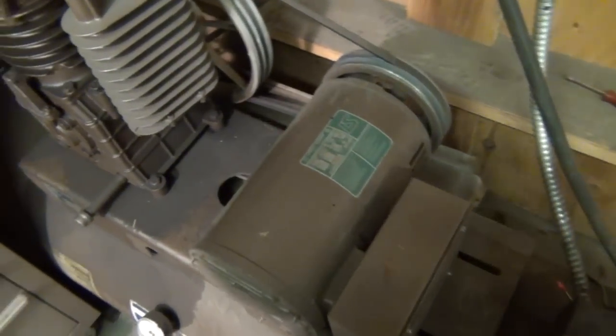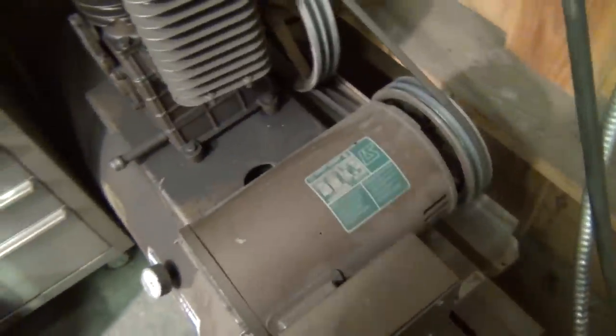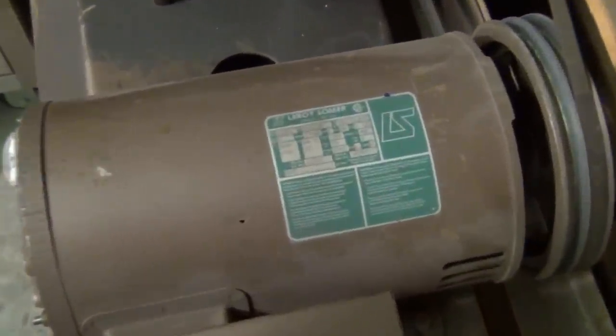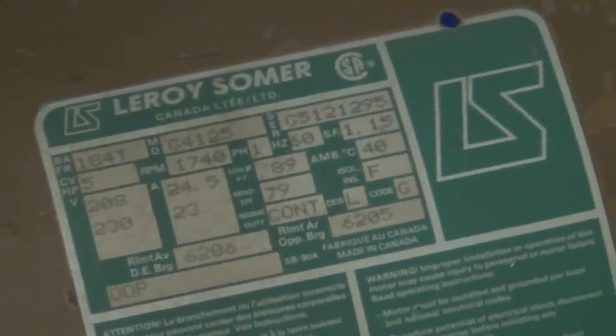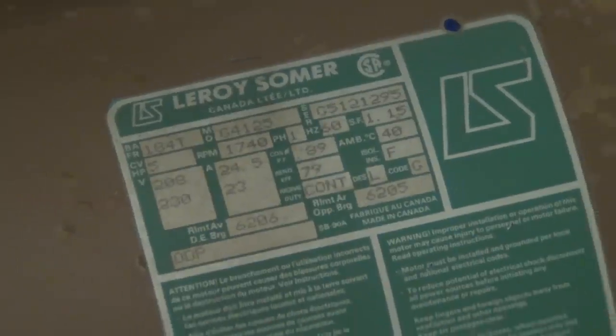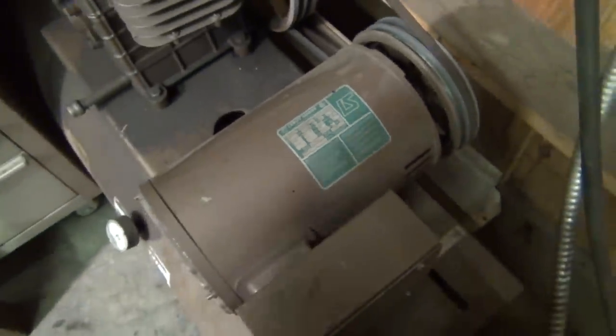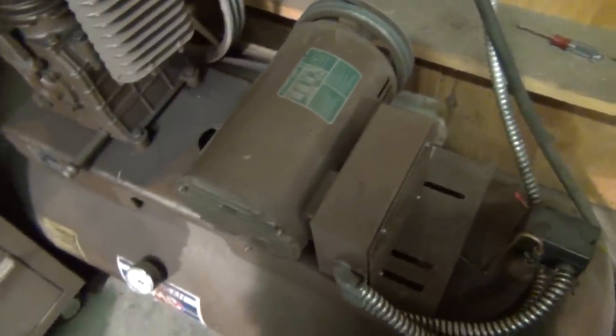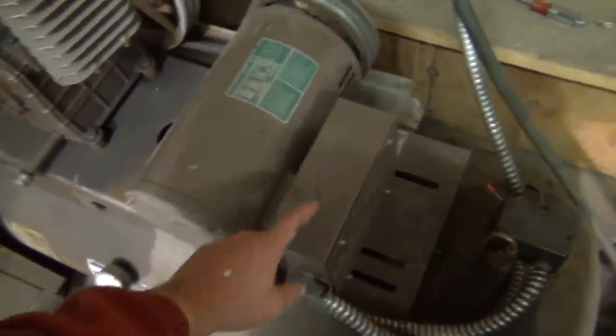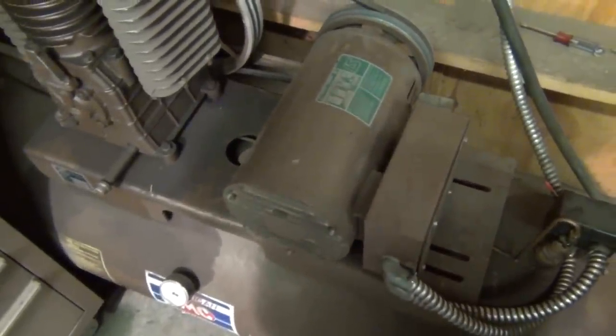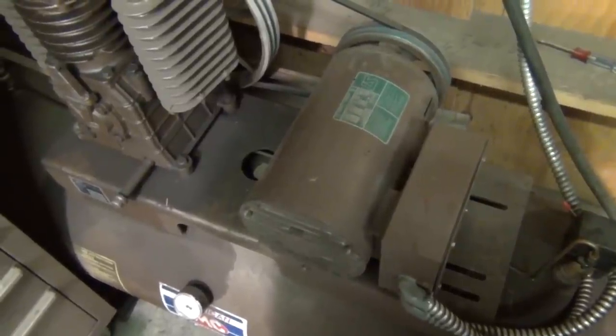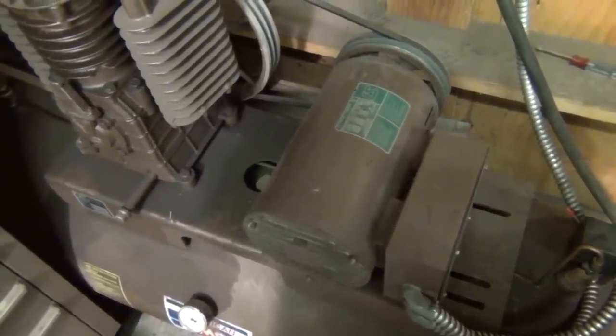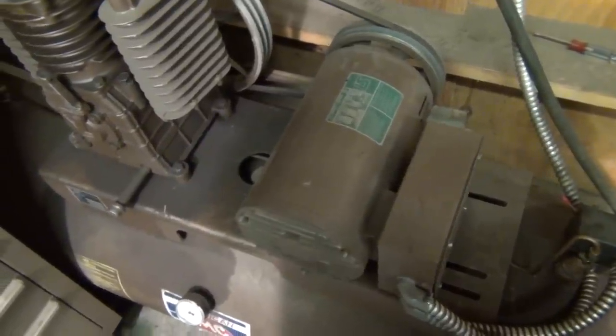So this is a single phase 5 horsepower 1800 RPM motor, and that's a real 5 horsepower, not the phony 5 peak horsepower you see on all the machines at the big box stores. And it's a 240 volt single phase motor, so that's actually a capacitor start and capacitor run motor. There's a couple of big capacitors in here and I suspect that just with my experience with electric motors that start capacitor is bad. So we'll go ahead and take that cover off and do some troubleshooting there.